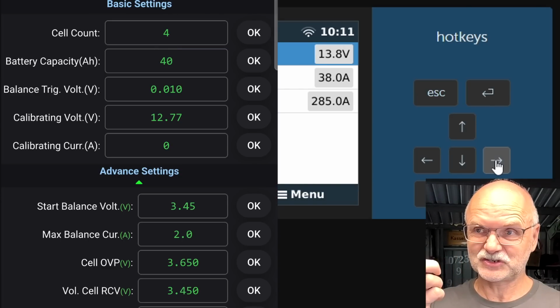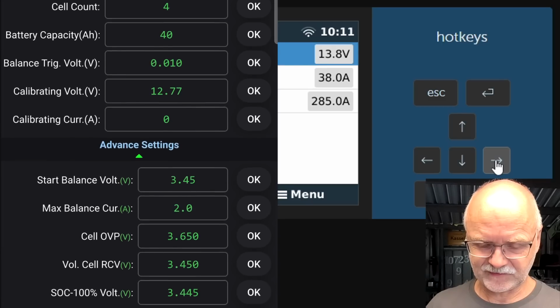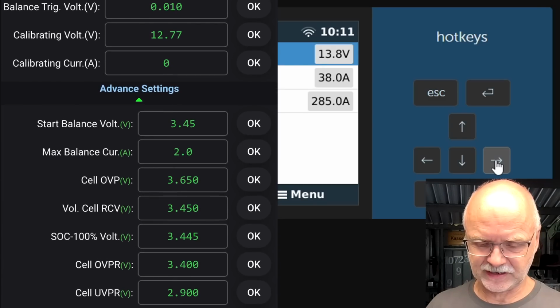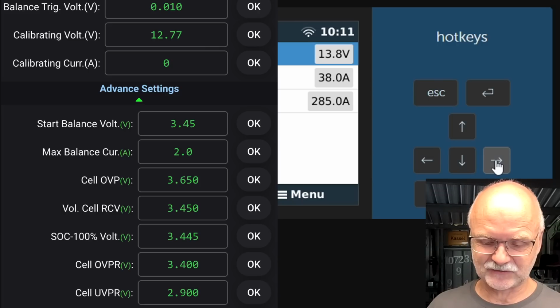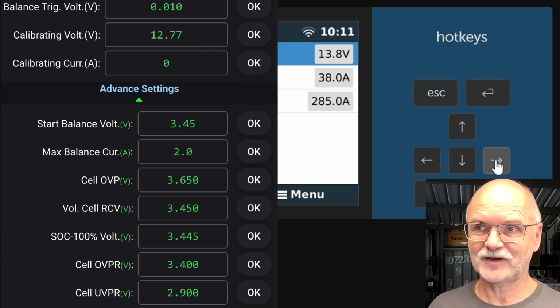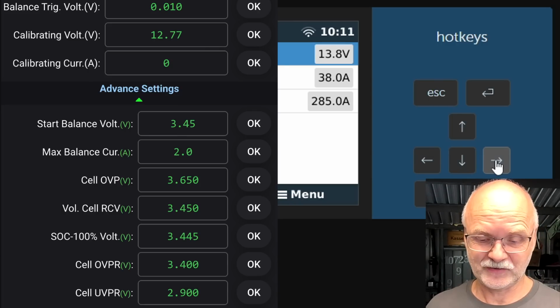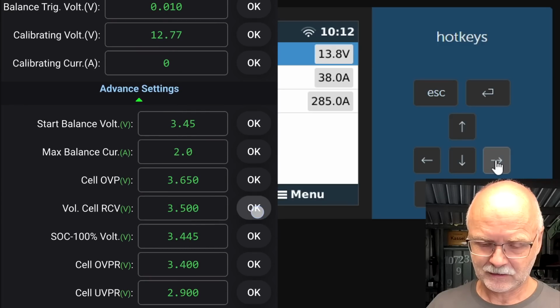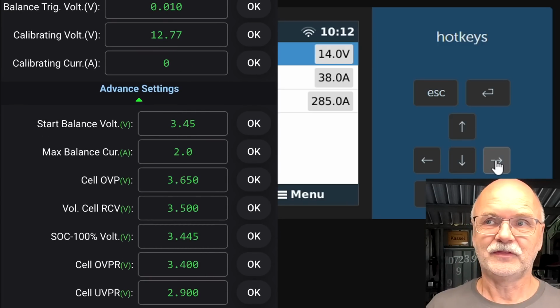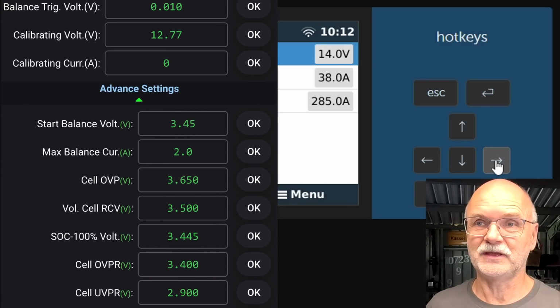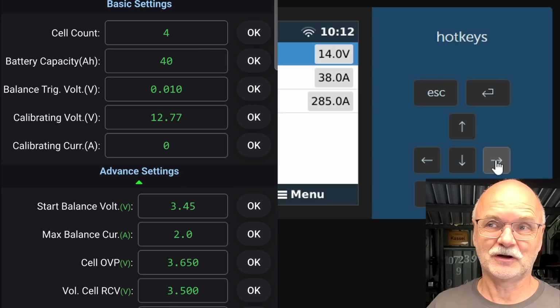Now the CVL has changed on the screen, and we can set the CVL here, voltage cell RCV, the requested charge voltage. 3.45 times 4 is 13.8. If I change this one here to 3.5, for example, click OK, you will see the requested charge voltage from the inverter, from your charger to the battery, will actually change.